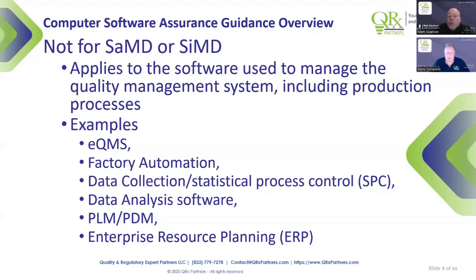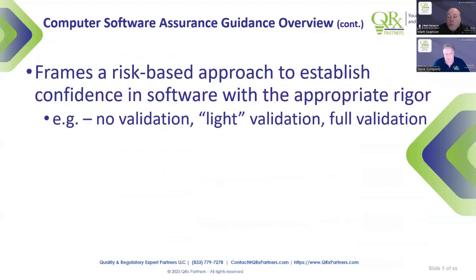Continuing on this theme, this to me is the most important part of this. And I think it's what makes this a really good guidance from the FDA: it's framing a risk-based approach. Because for anybody who's familiar with the old software life cycle guidance for validation that most people were trying to use because it had one section at the end to talk about non-product software, it was always like, well, how much validation, right? It got really confusing to try to figure that out.